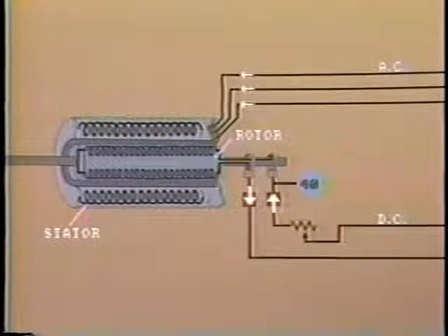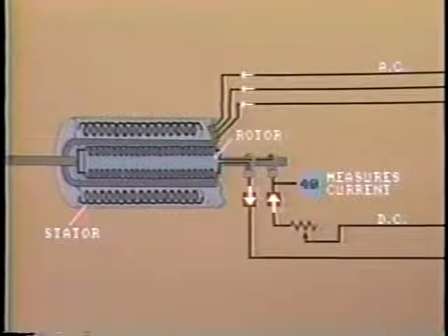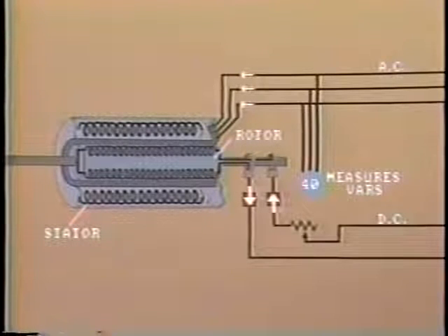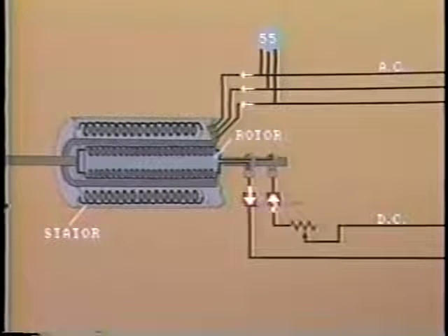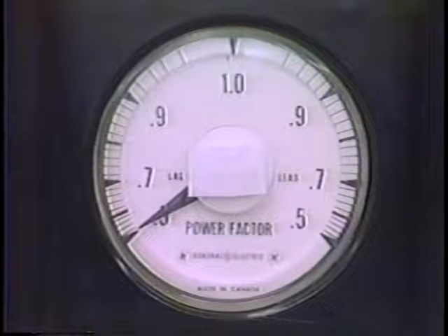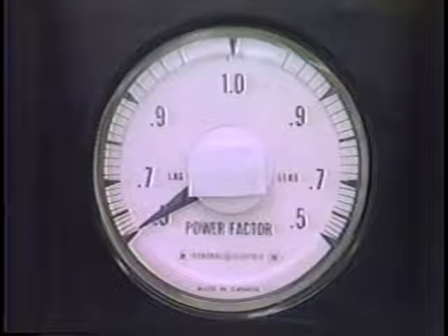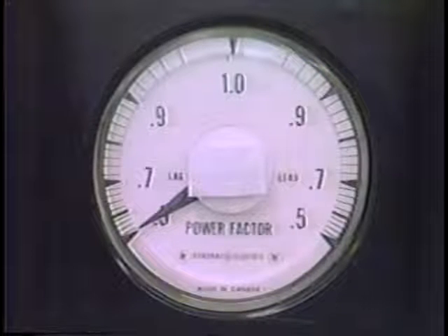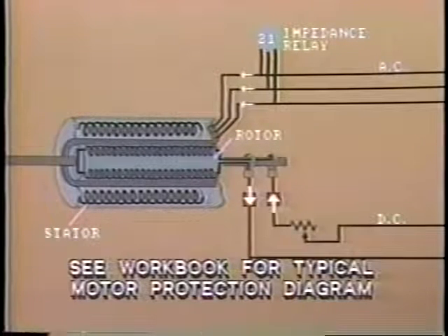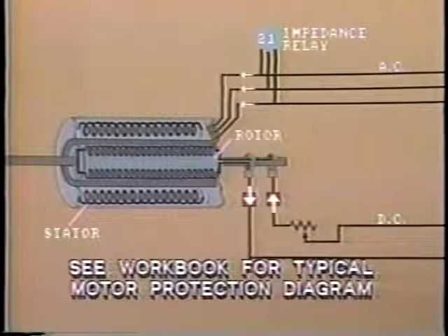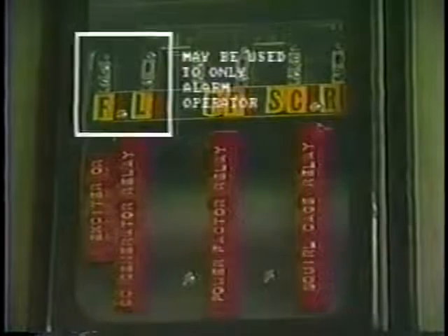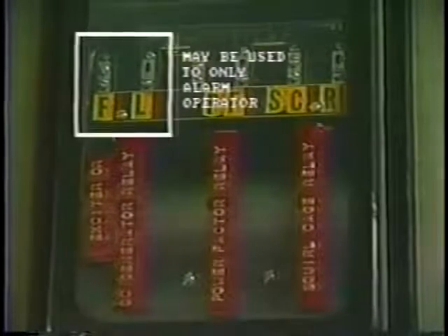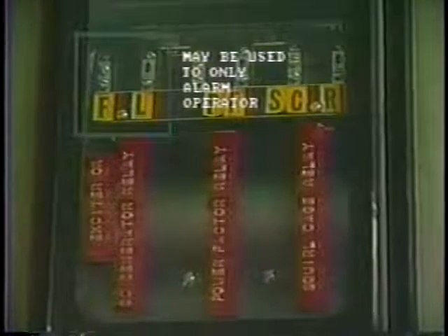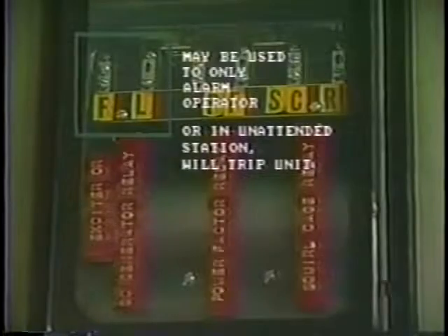The loss of excitation relay operates by measuring current in the excitation circuit or by measuring the flow of VARs into the stator windings. A power factor relay, 55, is often used, set to operate when power factor falls below about 0.5 lagging. Alternatively, an impedance relay may be used as described in our earlier discussion on generator protection. The loss of excitation relay may be connected to only alarm the operator so that he may restore excitation. Alternatively, in an unattended station, it will trip the unit.